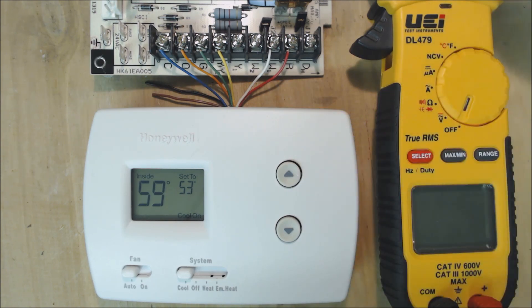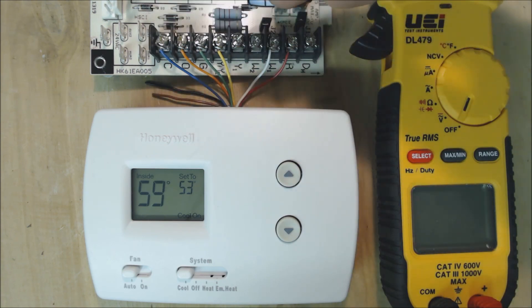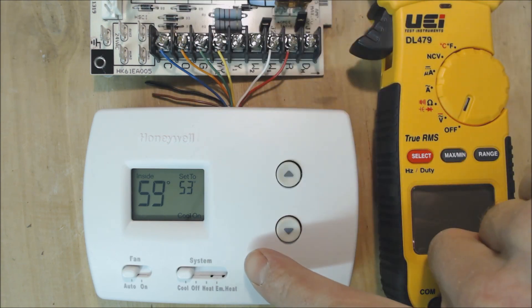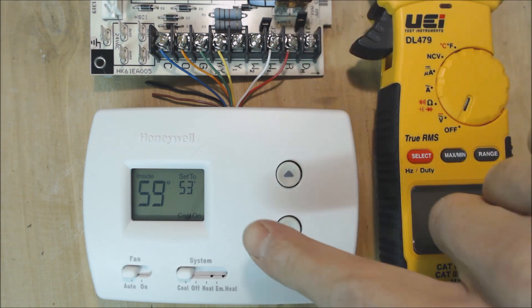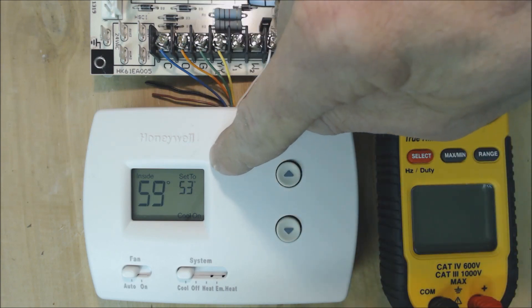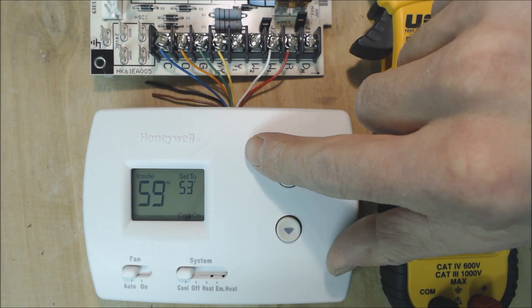Right now we have this air handler control board plugged in, and we are sending 24 volts to the thermostat. This R wire is 24 volt power that goes to the thermostat and supplies power, and it finds its way back through the common wire, which is C. So that's how the thermostat is being powered.